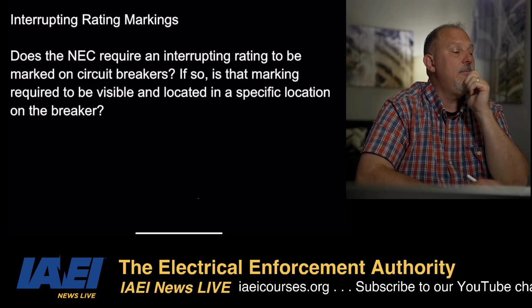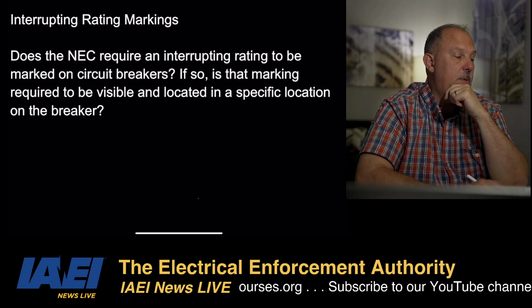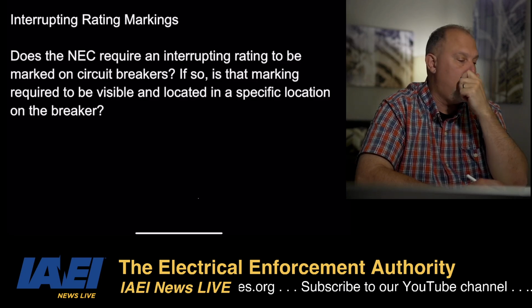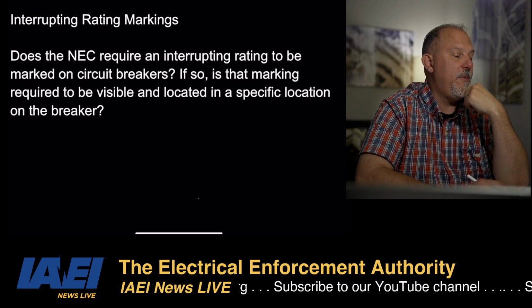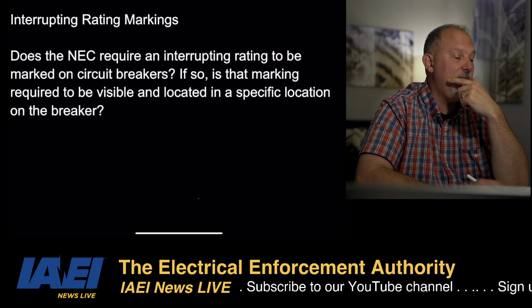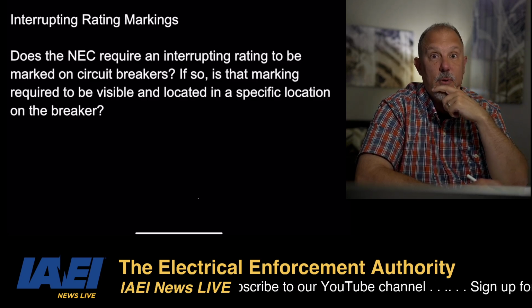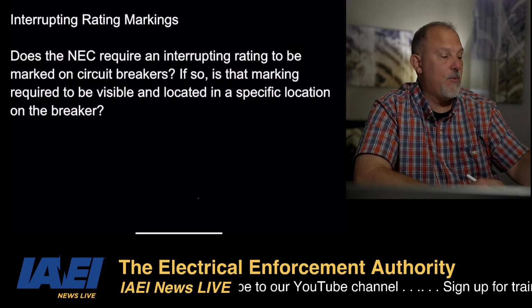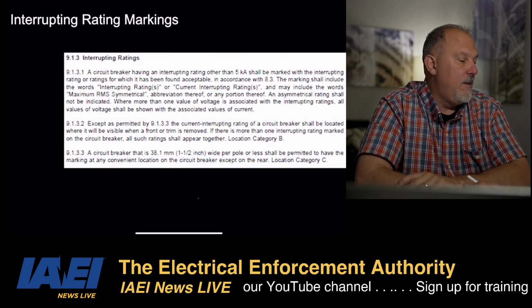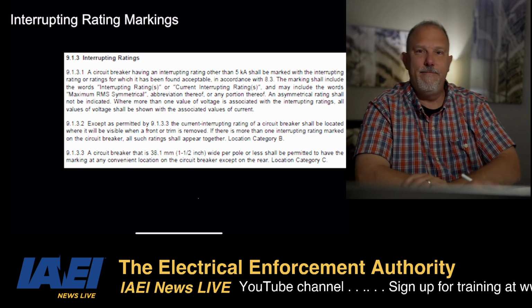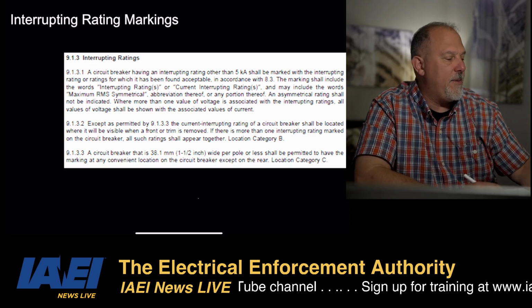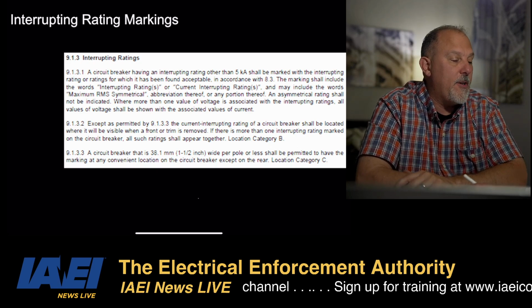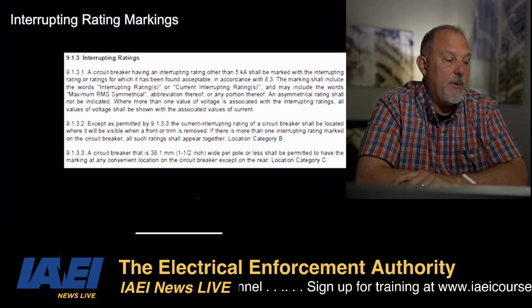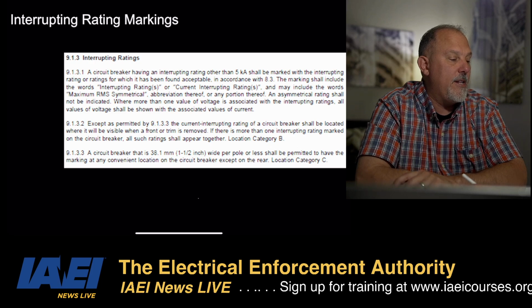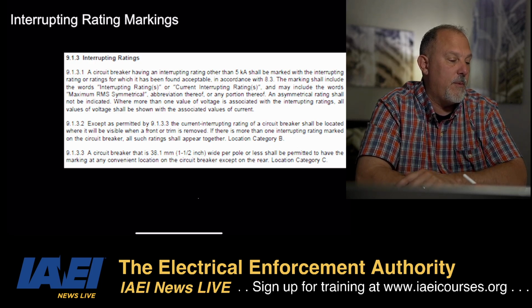Does the NEC require an interrupting rating to be marked on the circuit breakers? If so, is that marking required to be visible and located in a specific location of the breaker? Good question. Interrupting ratings: a circuit breaker having an interrupting rating other than 5,000 amps shall be marked with the interrupting rating or ratings which has been found acceptable in accordance with the standard.